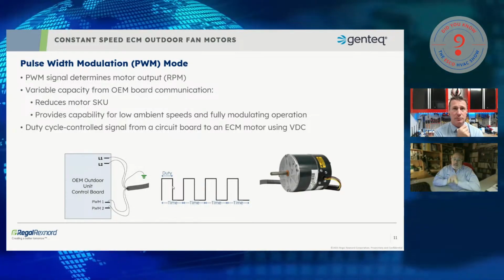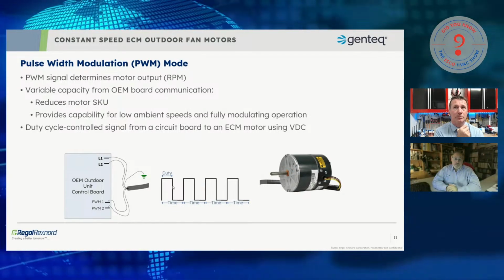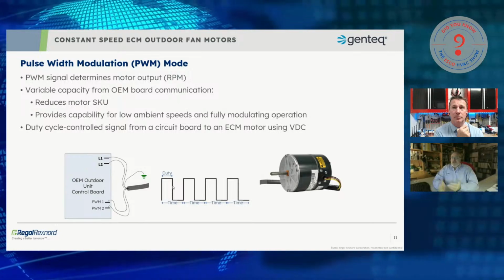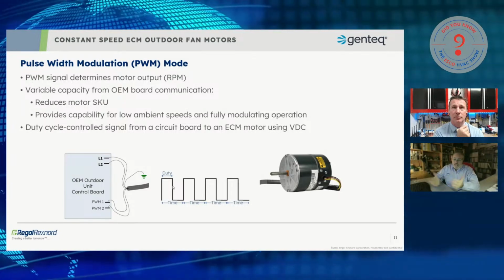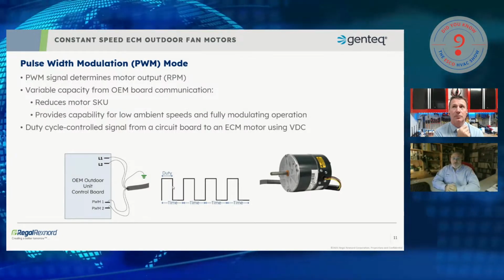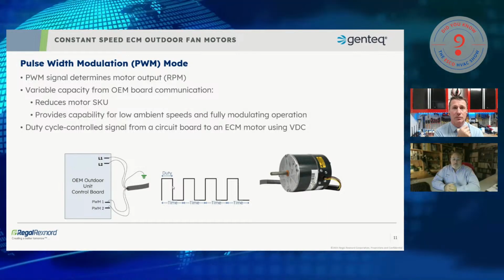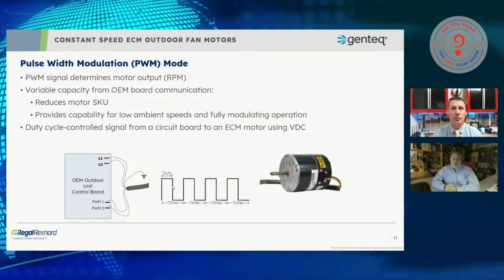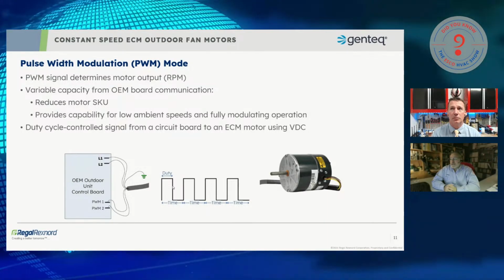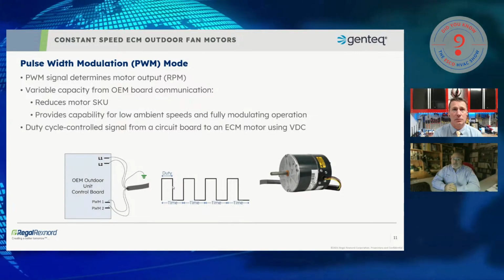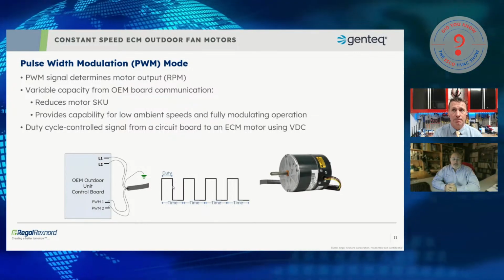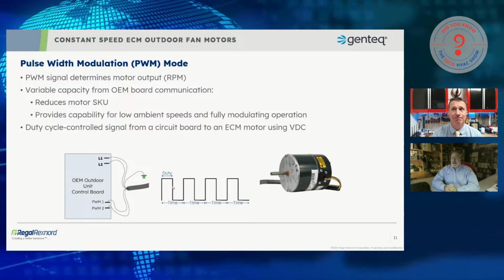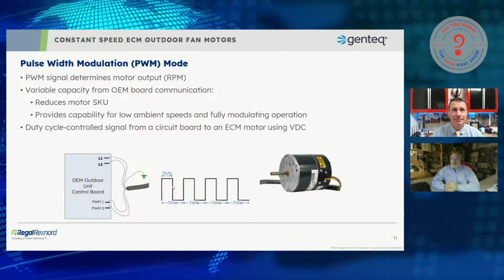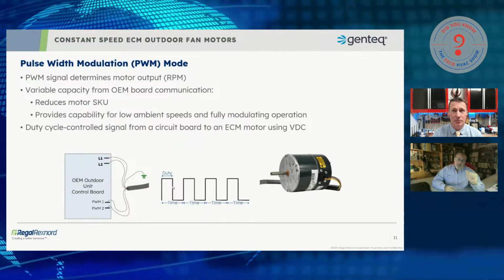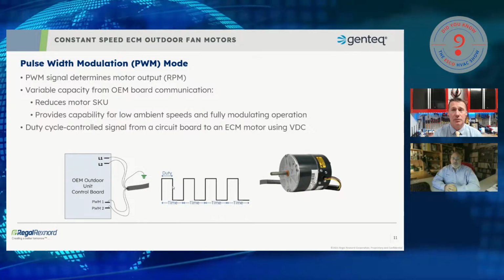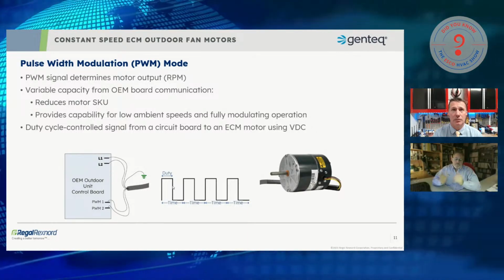And they also now have unlimited speed choices on the motor. If it's a two-stage system, they only need 2 speeds. They're kind of squandering all this wonderful value. But if they want to put a low ambient speed, they just program another PWM value. If they want to use this on a modulating system, and those are coming. No, they're not. They're here. They can simply modulate that PWM signal from the lowest end all the way up to the highest end to follow the demand of the compressor output of the system.